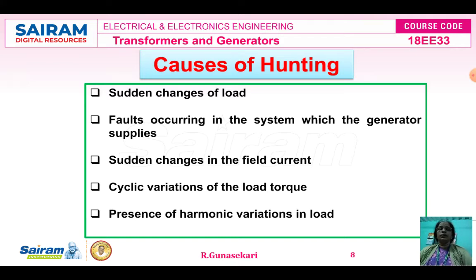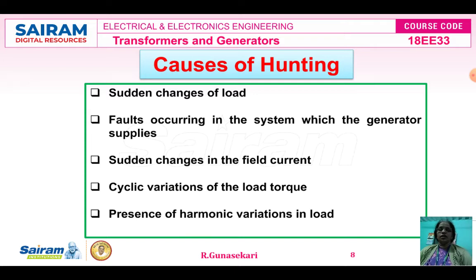If the speed varies, the frequency is mismatched and we cannot synchronize the synchronous generator to the bus bar. The fourth cause is cyclic variation of the load torque — based on the daily load curve, the load torque characteristics show an increasing and decreasing cyclic pattern based on the load used by customers. The fifth cause is the presence of harmonic variations in load; with AC power supply, odd and even harmonics are present, causing hunting in synchronous generators.